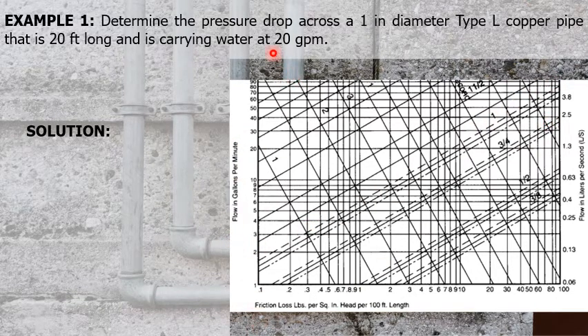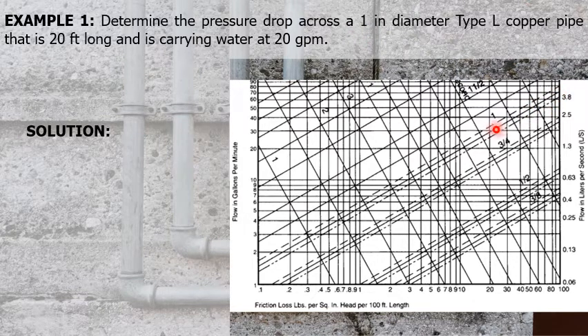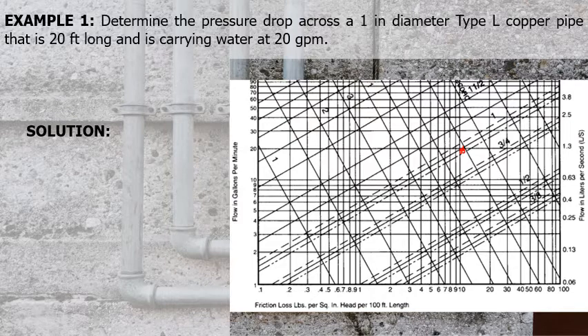So we have 20 GPM, and the 1-inch diameter is this diagonal line. This is the intersection of the two, approximately here. And we project that with the friction loss at the bottom, which is about 10 psi per 100 feet length.